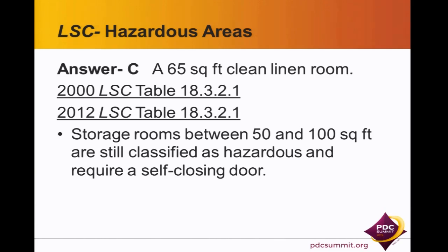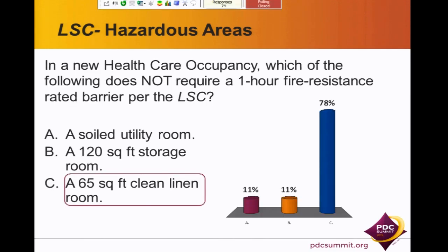Yes, sir. Doesn't it actually say, the first one, the right answer could also be A, because it says a soiled linen room, not a soiled utility room. I know most of the time they're using utility rooms for linen rooms or trash rooms, but technically doesn't it say linen room? It does, but the intent of this really was for the soiled linen. It really is to show that the soiled linen utility rooms of any size require that 1 hour.